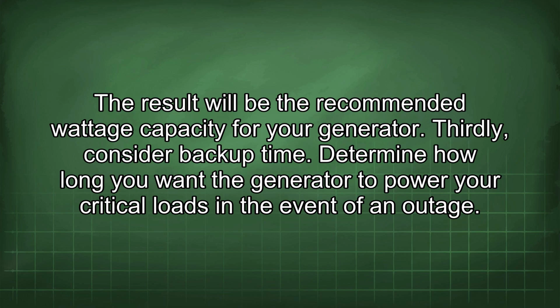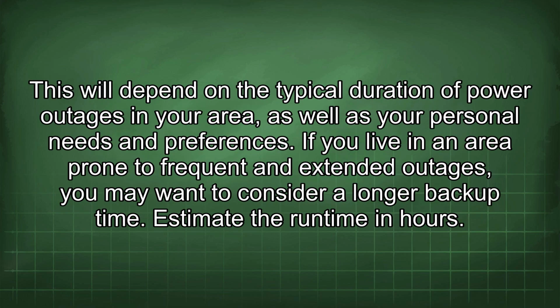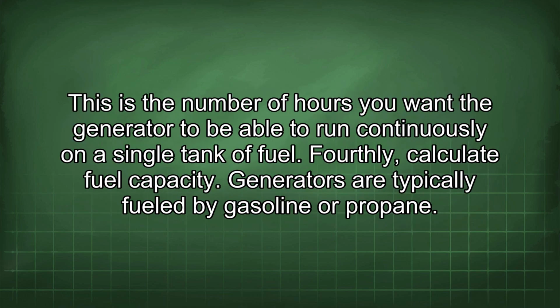Thirdly, consider backup time. Determine how long you want the generator to power your critical loads in the event of an outage. This will depend on the typical duration of power outages in your area, as well as your personal needs and preferences. If you live in an area prone to frequent and extended outages, you may want to consider a longer backup time. Estimate the runtime in hours. This is the number of hours you want the generator to be able to run continuously on a single tank of fuel.